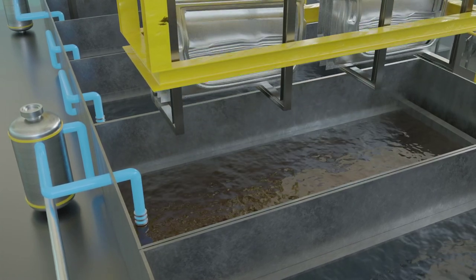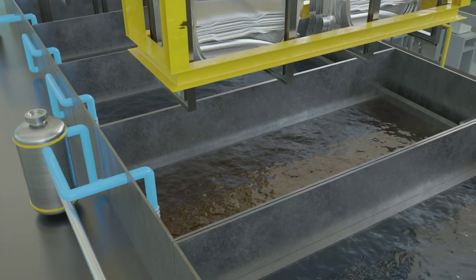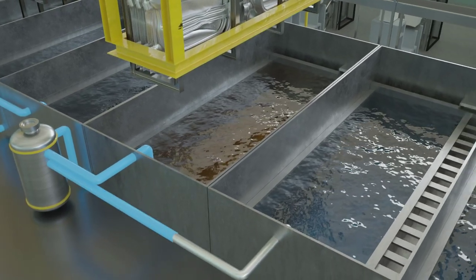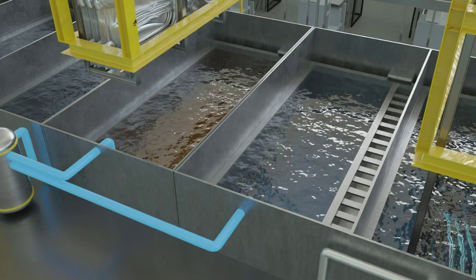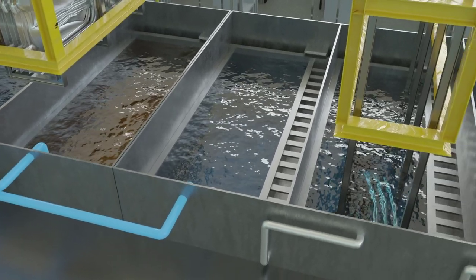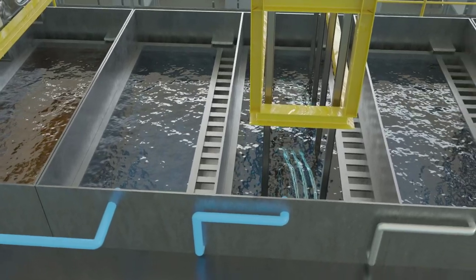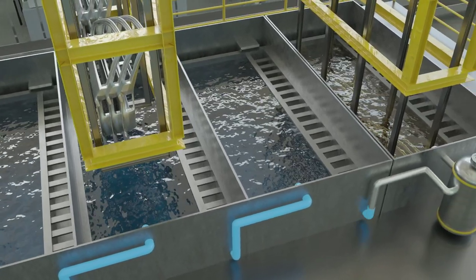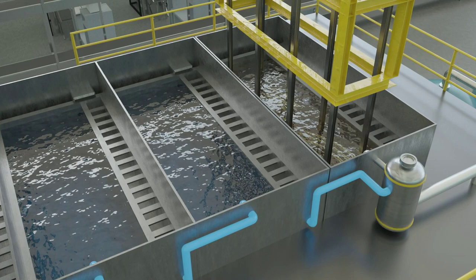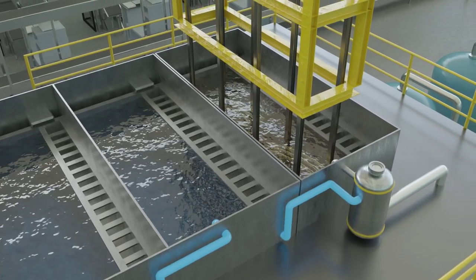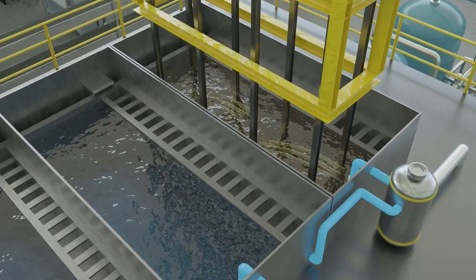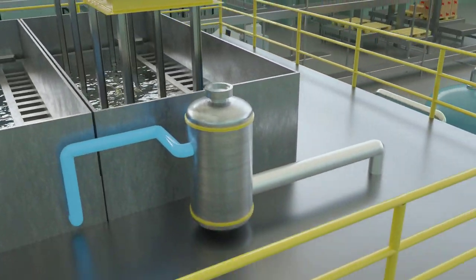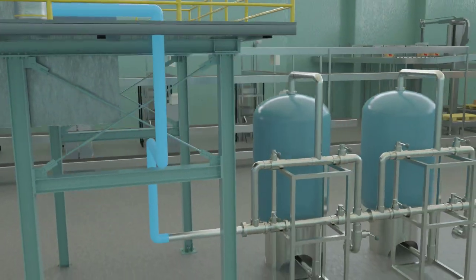However, the water from the buffer storage not only compensates for the losses in the degreasing bath, it also flows to the flushing cascade in front of it. The water flows through this cascade according to the same principle. And here, too, the water from the last cascade ends up in a buffer storage tank, and part of this flows back into the degreasing in front of it. Here, too, some of the chemicals are recycled. Only a remainder of the water is discarded and is treated in a separate wastewater plant before it is discharged into the sewer system.